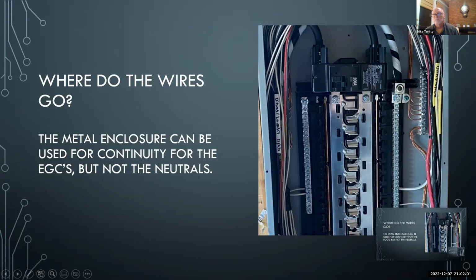I'm probably confusing people, but basically that rule was changed, I think, in 99, maybe. I don't know, but that's not important. That confuses a lot of people because on the service panel they'll see equipment grounds and neutrals all down through here, and they may see all equipment grounds here, some neutrals and equipment grounds here, and I have guys call me and call it out and say these equipment grounds aren't supposed to be on the neutral bar. In the service panel, they're fine. It's bonded. It's the same as that. Everybody understand that? Yes.